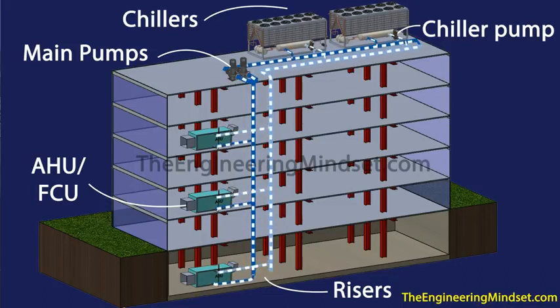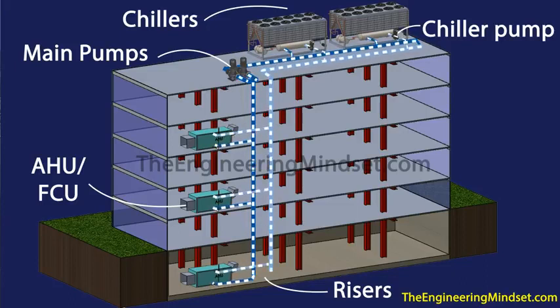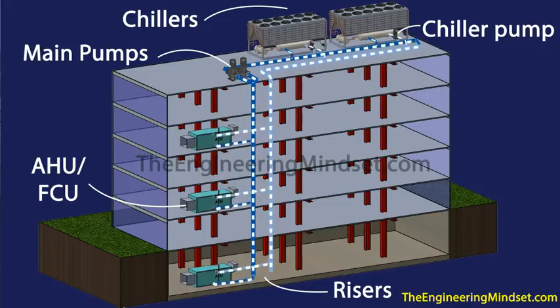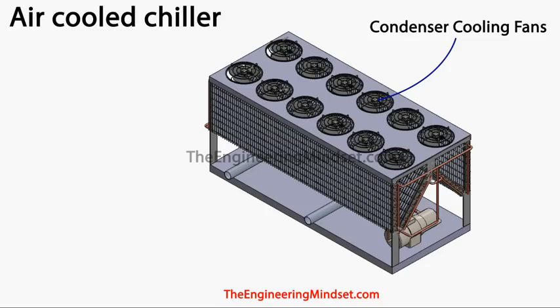So let's now have a look around the chillers to see the main components, and then after that we're going to have a look at a bit more detail on how they actually work. So first of all, if we look at the air-cooled chiller from an isometric view, you'll see that on the top are the condenser cooling fans. Now when these rotate, they suck air in, the ambient air from the outside, and they pull this in through these grills and through these holes, and also through these grills here. So they pull all this air in and then they push that air out through the top.